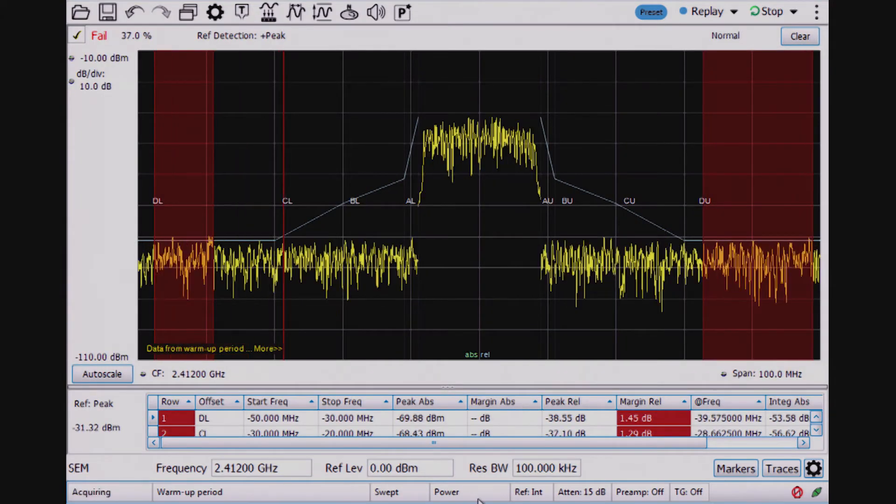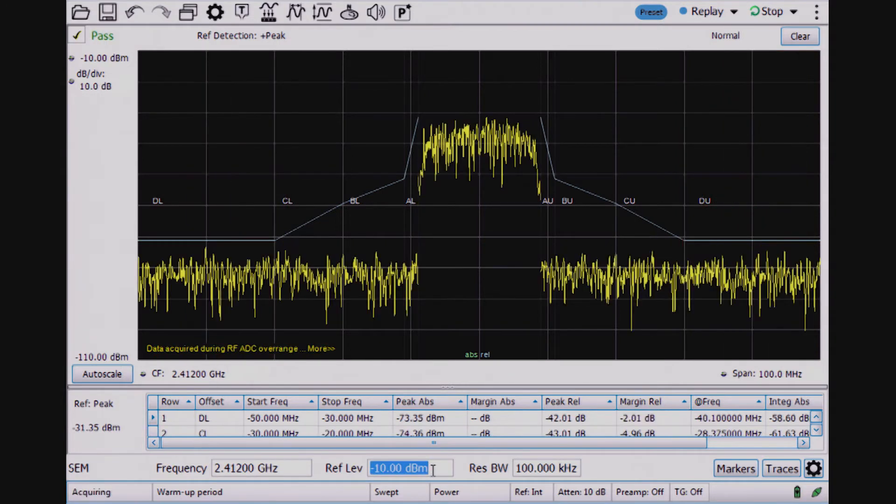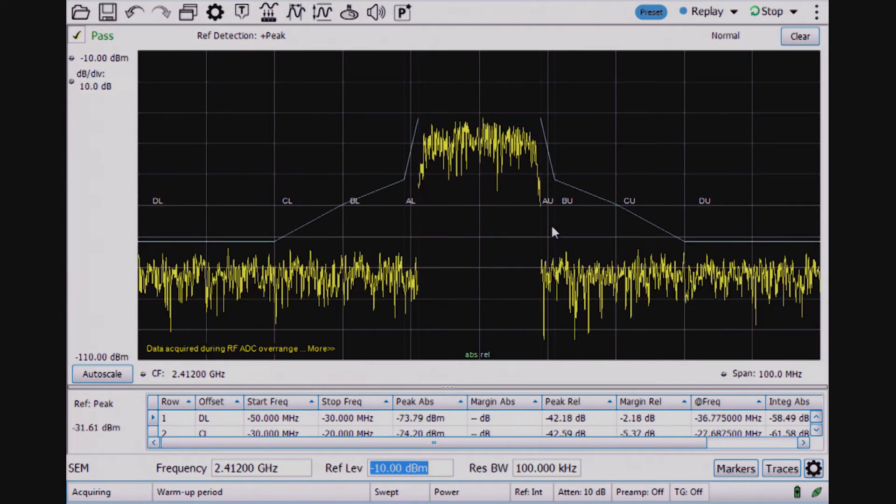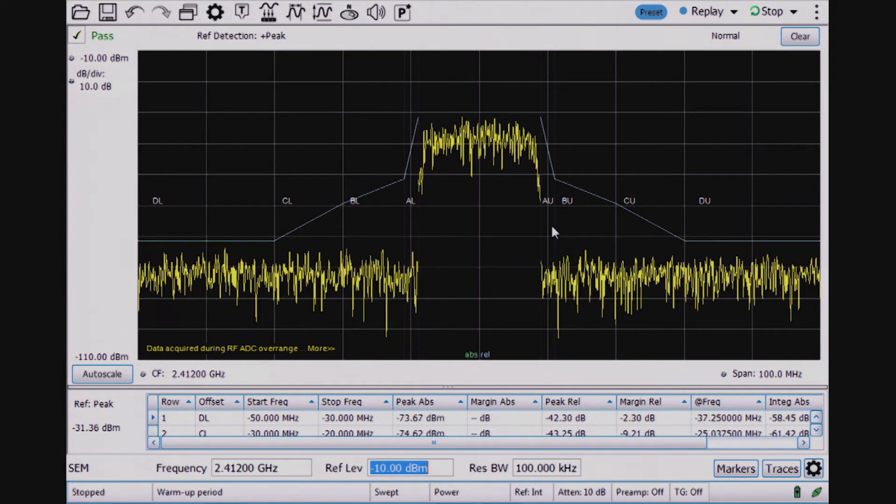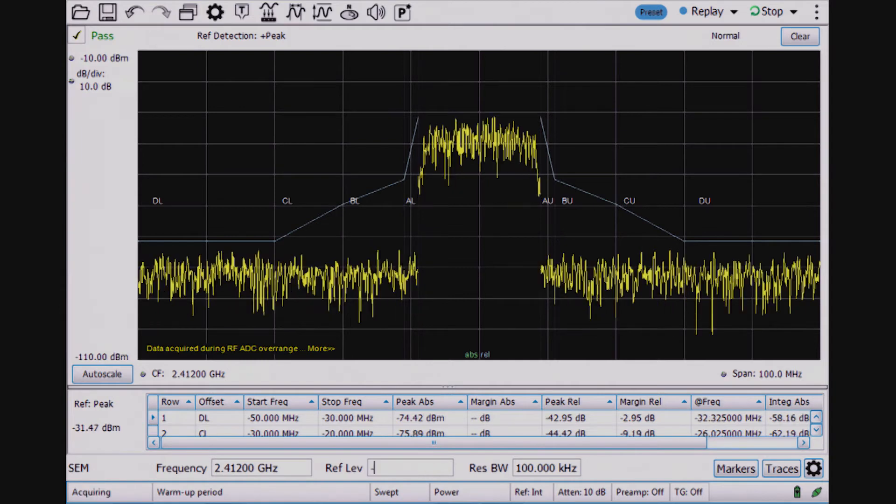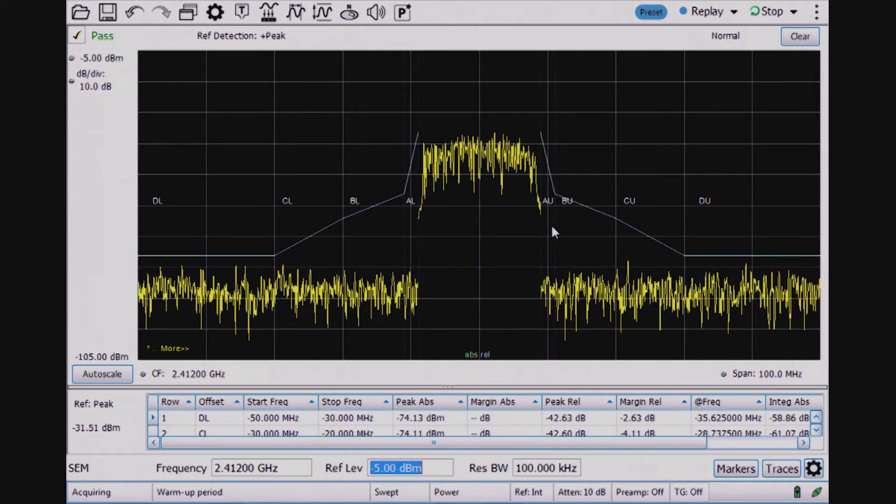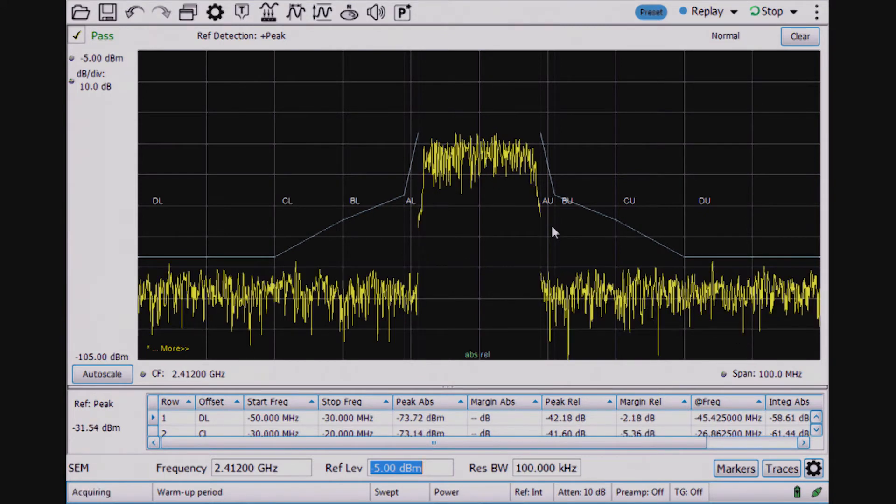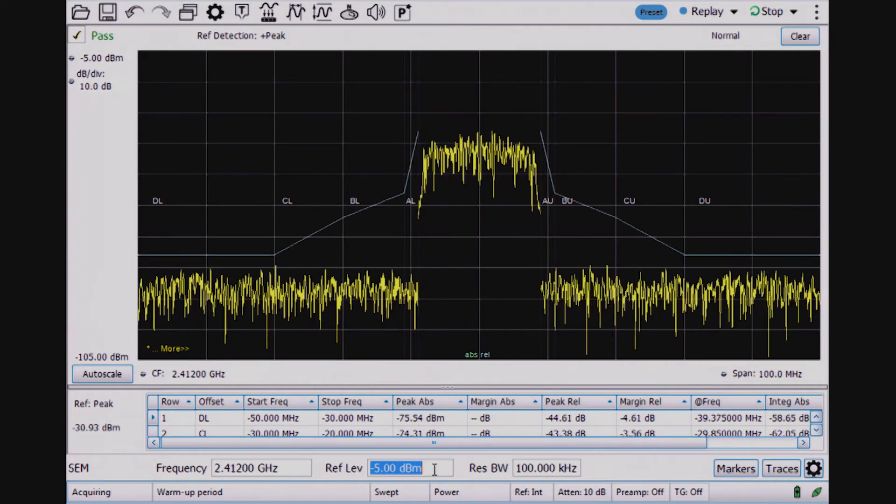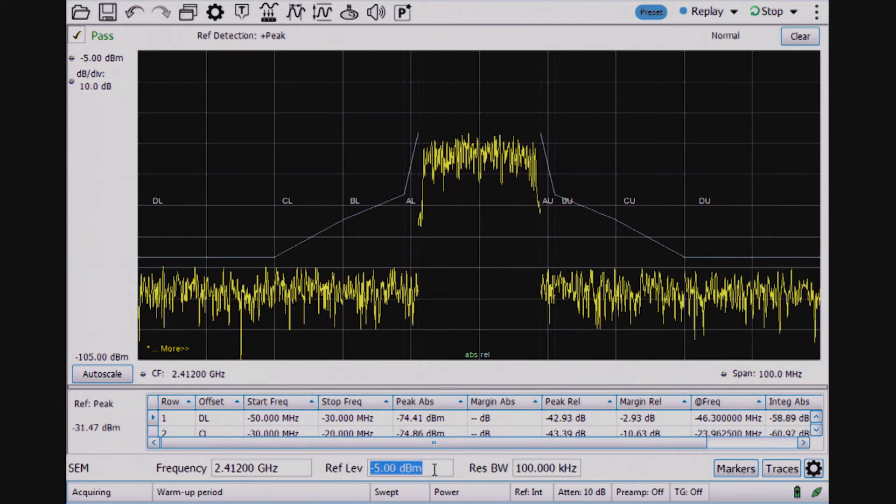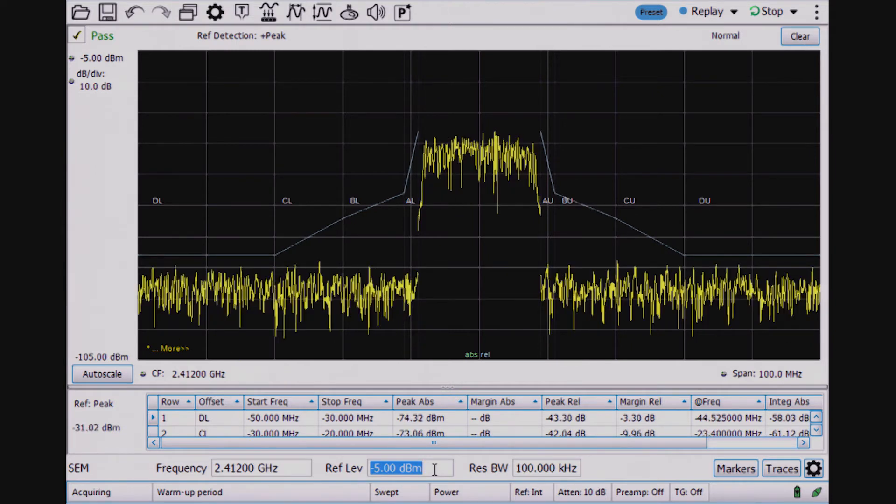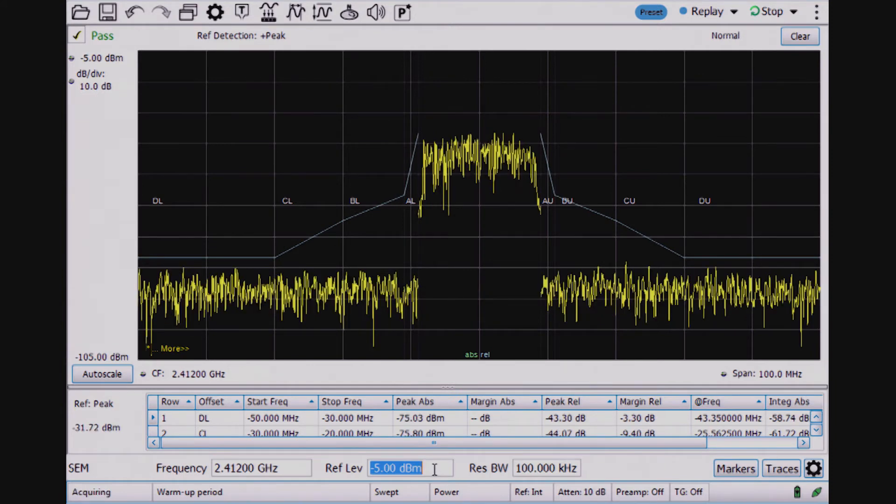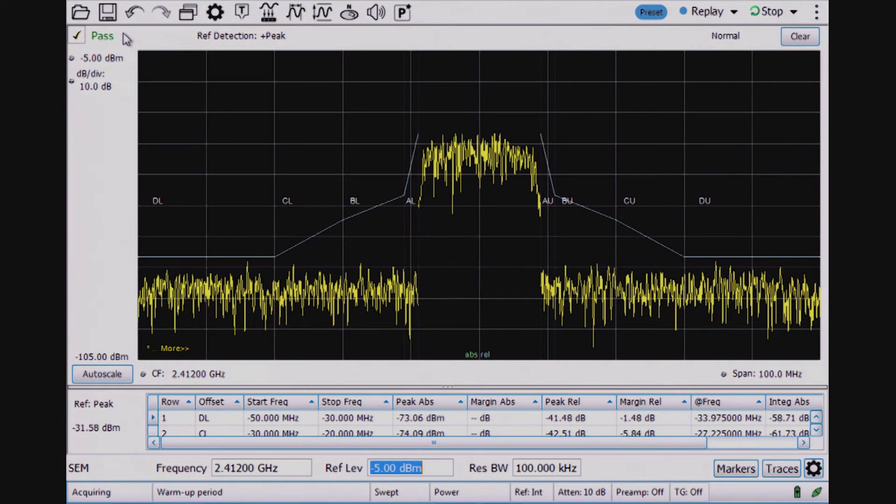I may need to adjust the reference level to make sure that I still trigger and have the range set up adequately. The reference level settings may be called out in the particular test, but I'm overranging. I need to avoid an overrange message. I went down to minus 10 dBm for the reference level at first and that was too low. Now I back off to minus five dBm for the reference level.